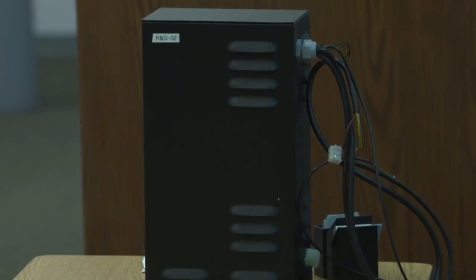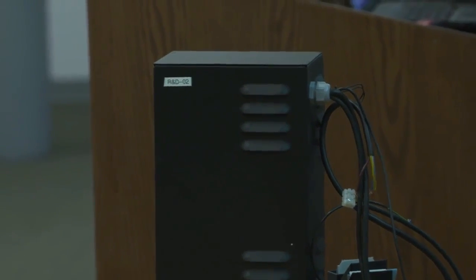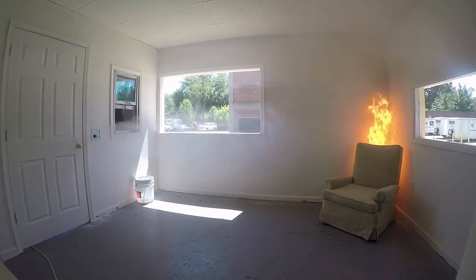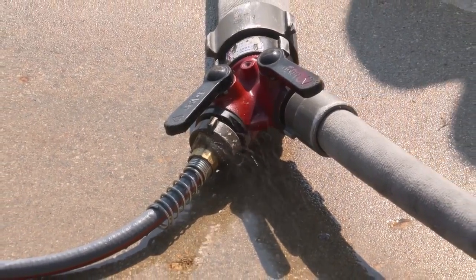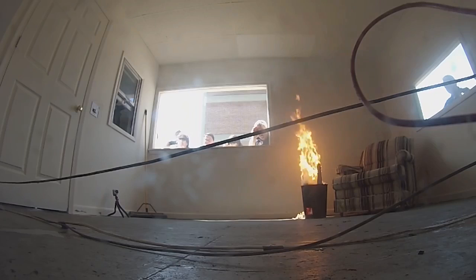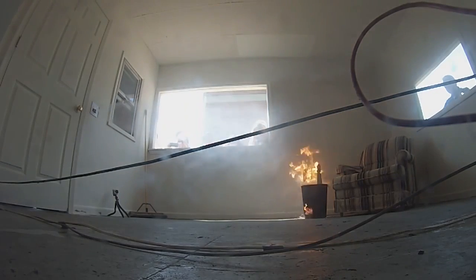We selected a small but powerful pump for our particular product. The main reason is that one of the biggest issues with traditional sprinkler systems is that you sometimes require expanding a main or bringing a main to get the amount of water required to suppress the fire. Water Mist is unique in that you really just use a small amount of water.